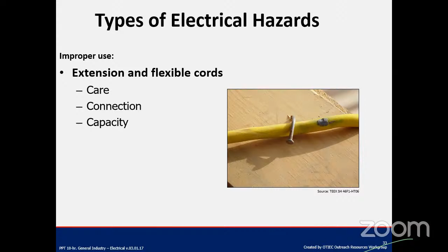The problem here is our confidence level, not competency. We are so confident thinking we didn't hammer the nail too much, we just slightly bent it so the cable doesn't move away. But what happens when you use a nail to hold a power supply cable? If something falls over the nail, or somebody steps over it, there's a possibility of further crushing the cable, which may damage it and cause overheating at that location. Because of that, the outer insulation will go bad, or the inner insulation will get damaged.